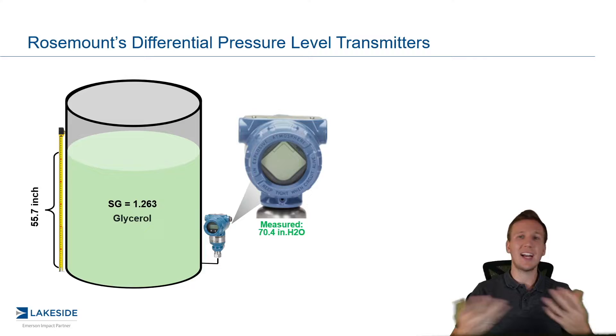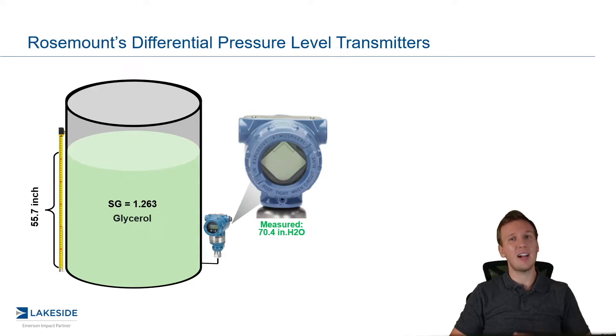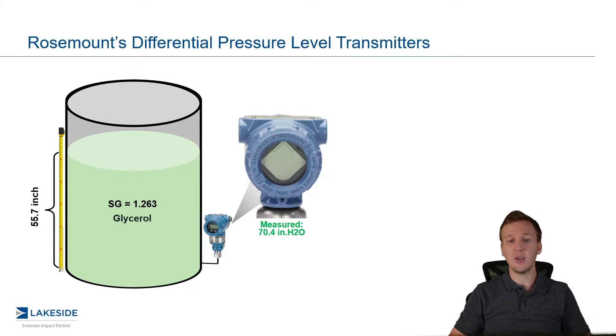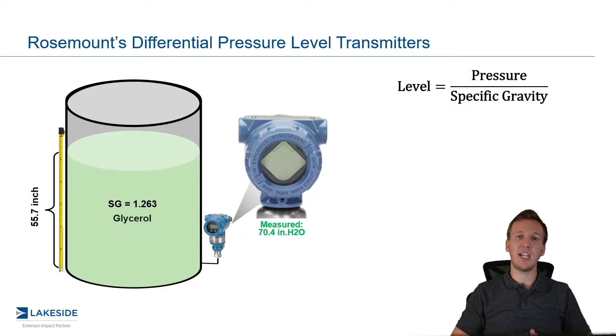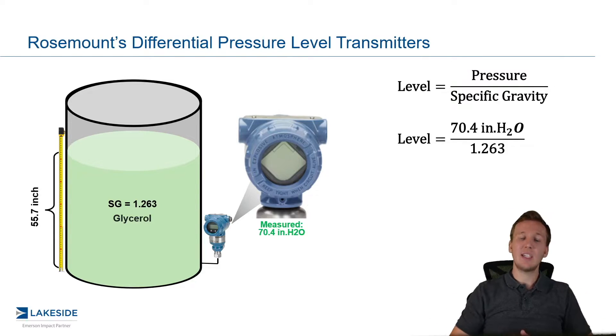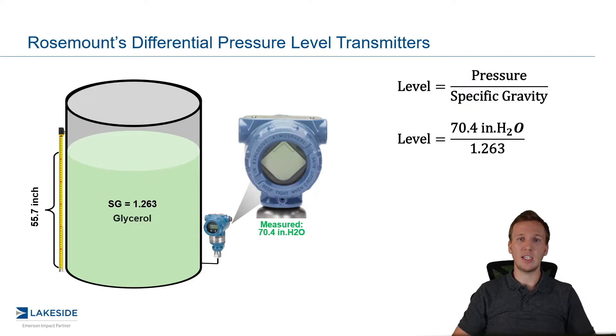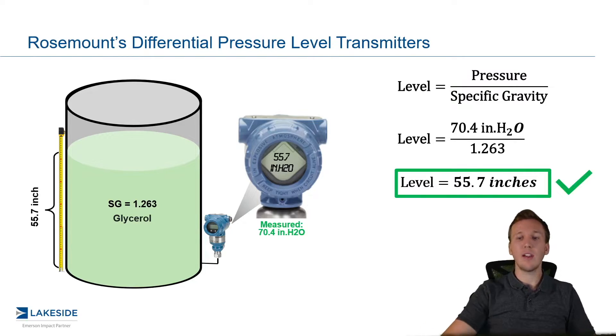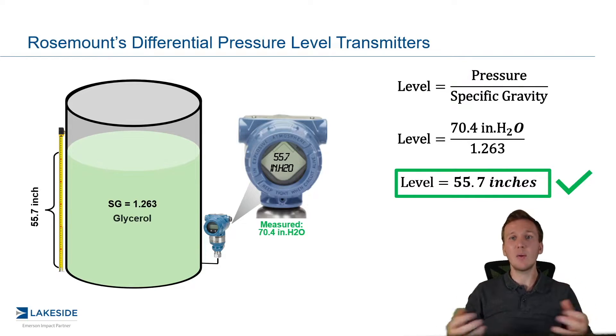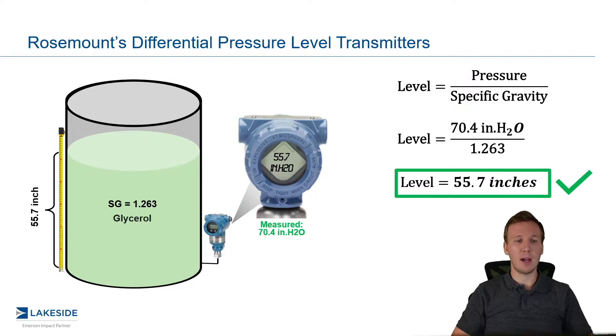So we need to take that into account. We need to tell the transmitter that it doesn't have water — it has glycerol. How do we do that? We simply take that pressure reading and divide by the specific gravity. In this case, we take that 70.4 inches of water, divide it by 1.263, and we are left with 55.7 inches of glycerol. And this is exactly what we want — a great level measurement from this gauge pressure transmitter.